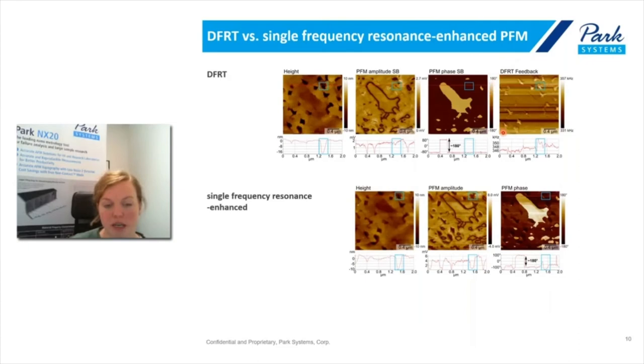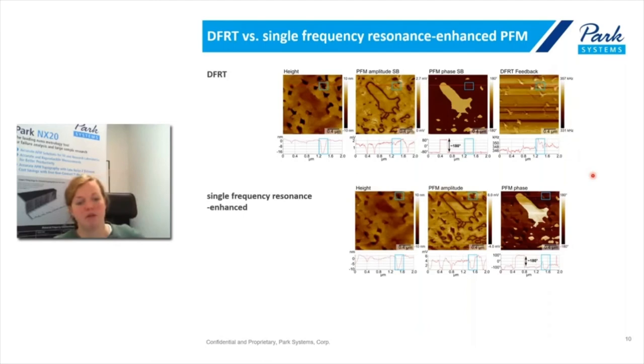Furthermore, looking at the DFRT feedback output, we have an additional measurement channel that gives us information on where the contact resonance shifts. In this case, the frequency channel essentially gives us topography information — a frequency change occurs whenever there is a topographic feature. But for materials with inhomogeneous nanomechanical behavior, the DFRT feedback signal can serve as an additional measurement channel.